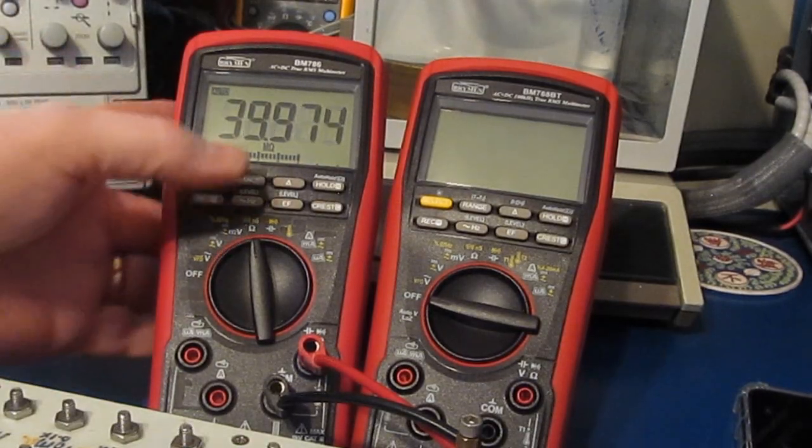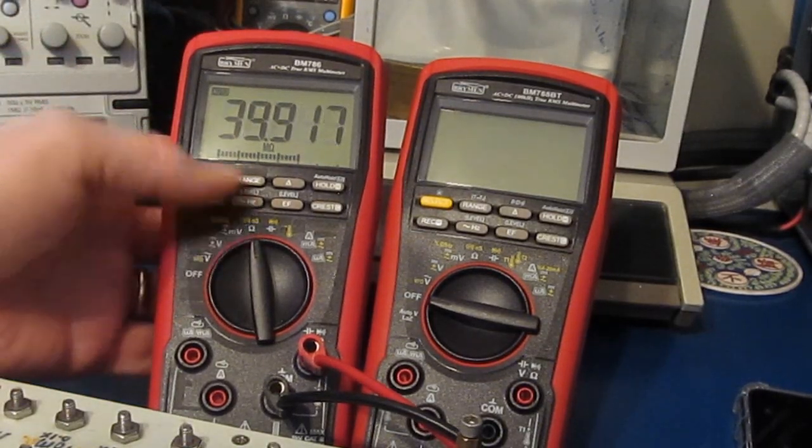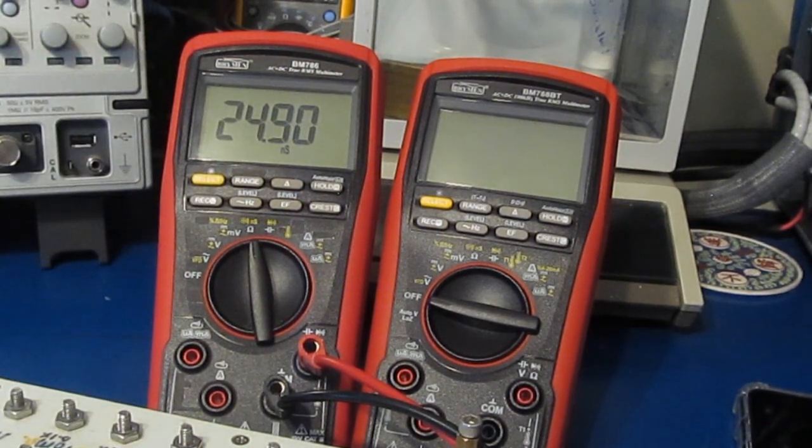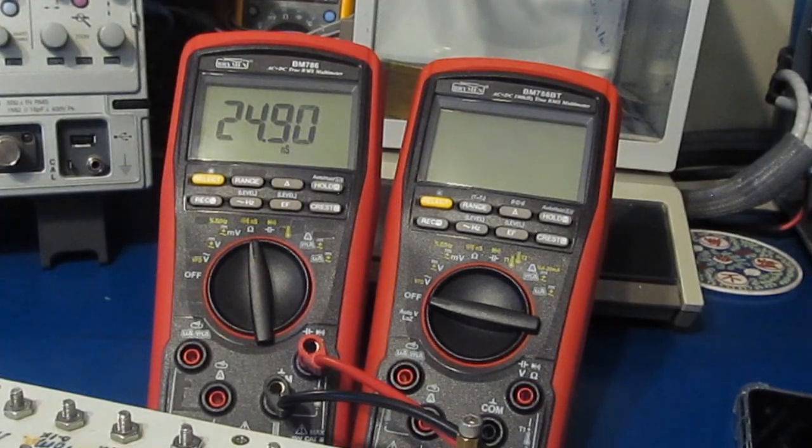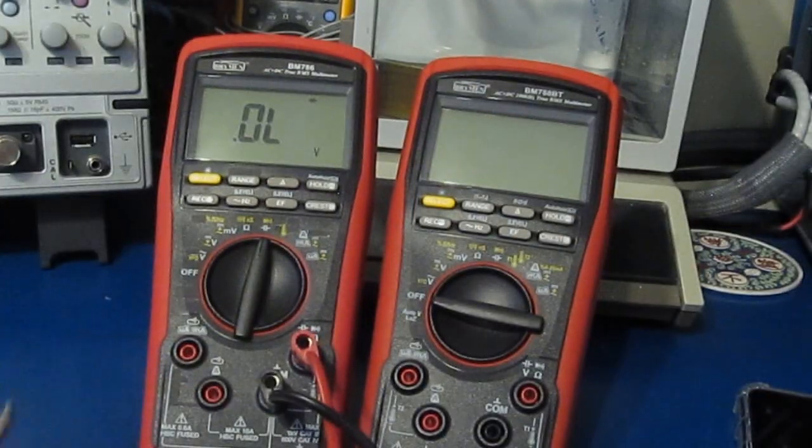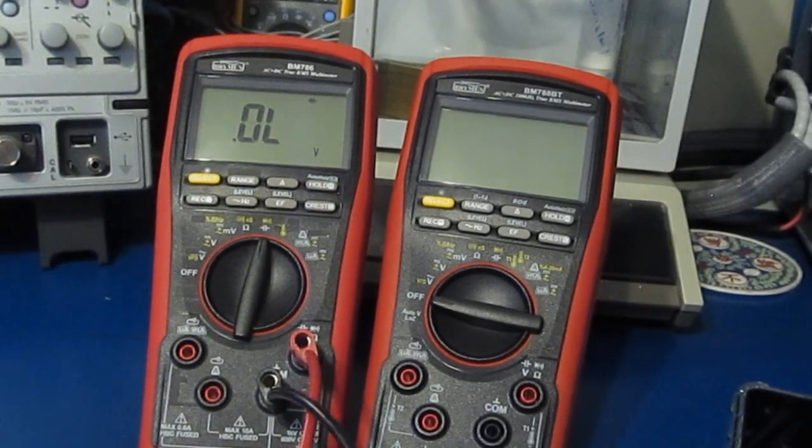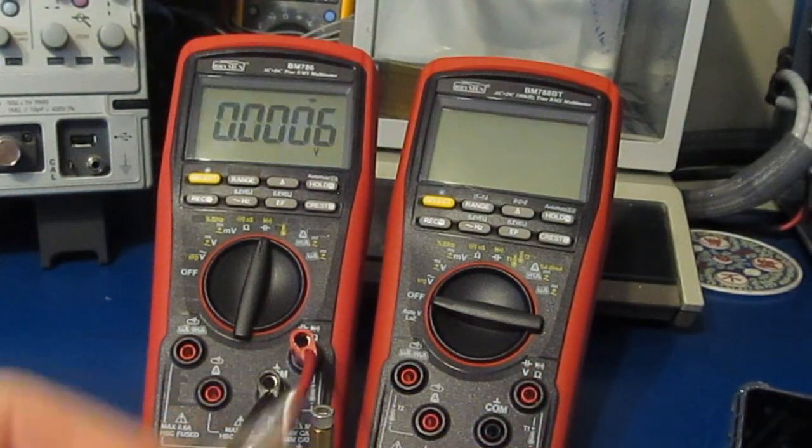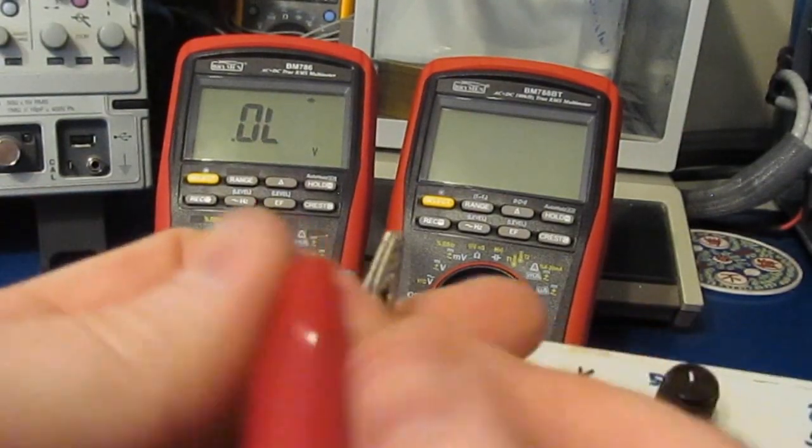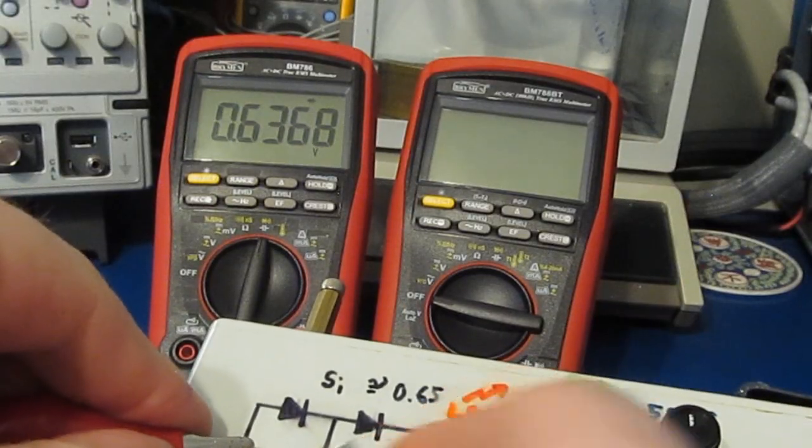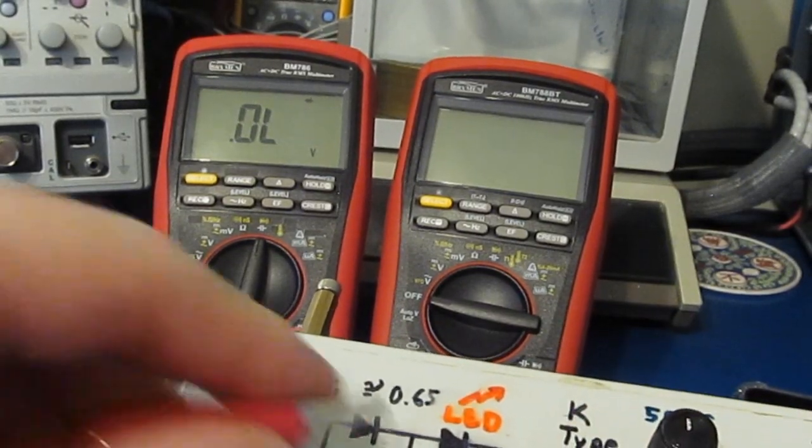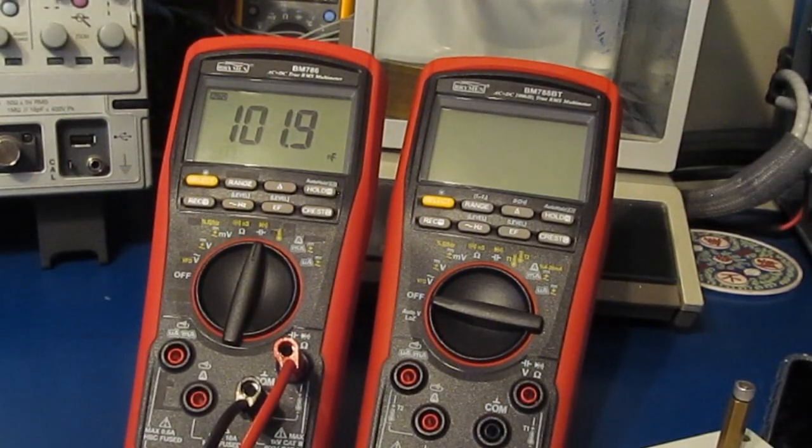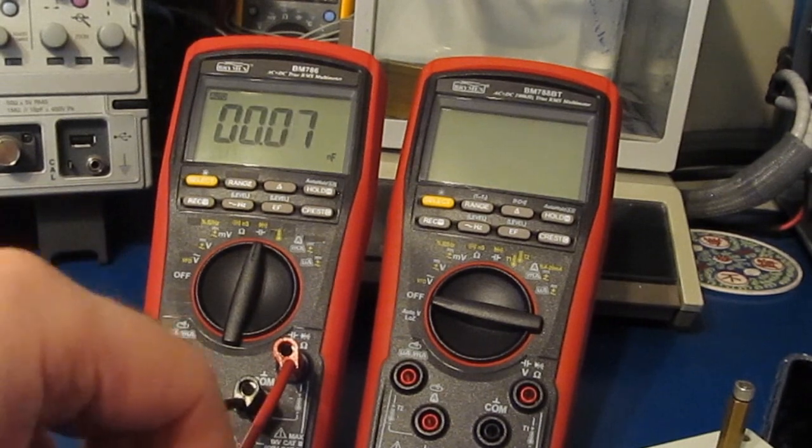This is our 40 meg. Again, this is a two percent part. And we're going to measure conductance. Should measure 25, and you can see it's fairly close. So here's our diode check mode. Again, before the alignment, this was reading 0.7 volts. With a short it should read zero.